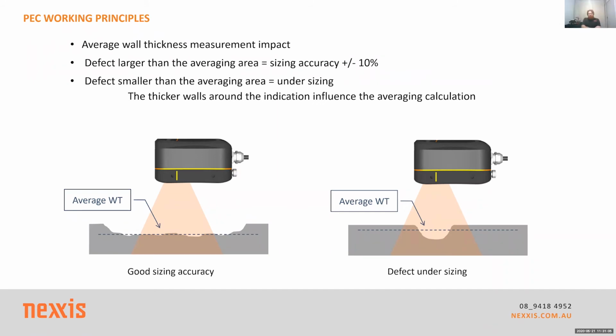Yeah. So frequency, Rick kind of touched on it. Frequency is not a thing with pulse eddy current as much. It's like if you had a torch and you're shining it on a surface, you're going to get a nice little round circle. That's your footprint. And realistically, what you're measuring is if I cut that circle out of the material. So it's a volumetric wall loss.